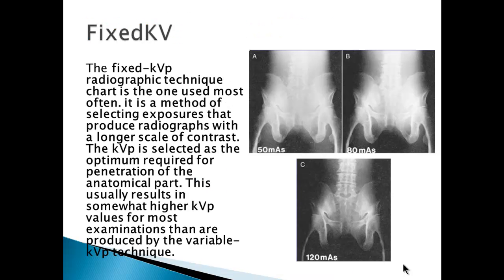The second type of technique chart is a fixed KV chart. Similar to the variable, the keyword here is fixed in that the KV will remain the same and the mAs in this case will change.